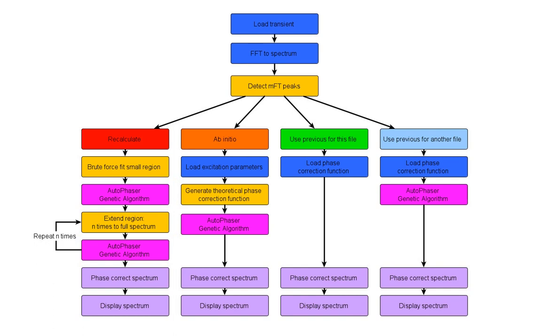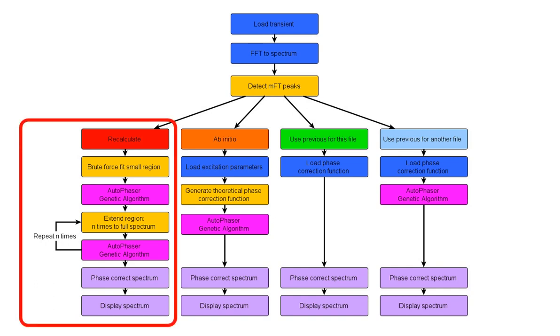Unfortunately you can't simply use the brute force method to fit the phase correction function over the complete spectrum in one step because there are too many potential solutions to search. This Recalculate route will work for both ICR and Orbitrap mass spectra, so let's look at this working for both of these types.